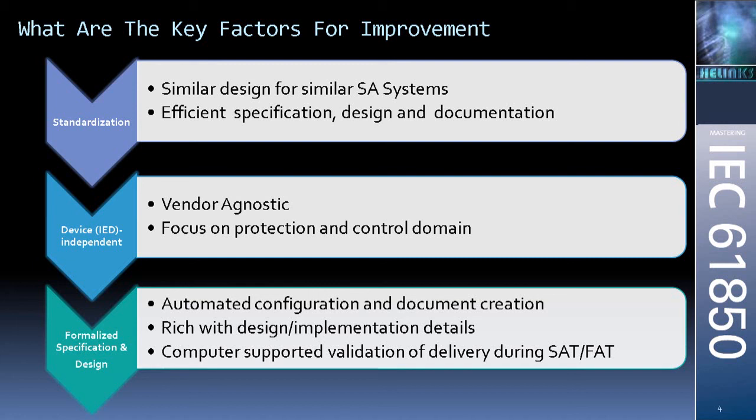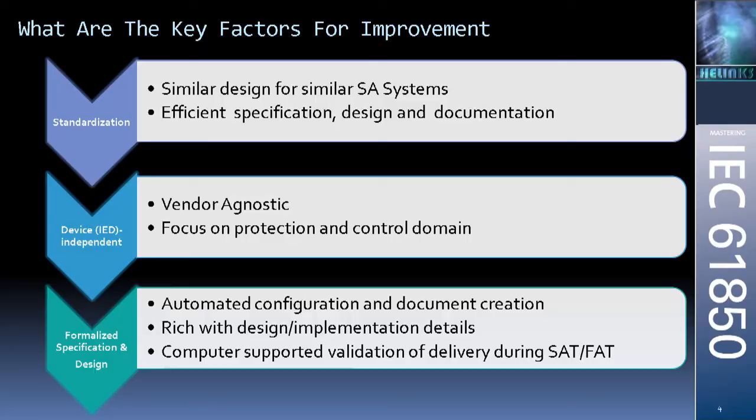But generally there are different vendors, and the relays change with time, but the primary equipment and the algorithms and design solutions of the utility remain stable, independent of the IED. If you think about distributed systems or monolithic systems, there too we have system design, we have algorithms, we have signal lists, but we do not have specific relays anymore.